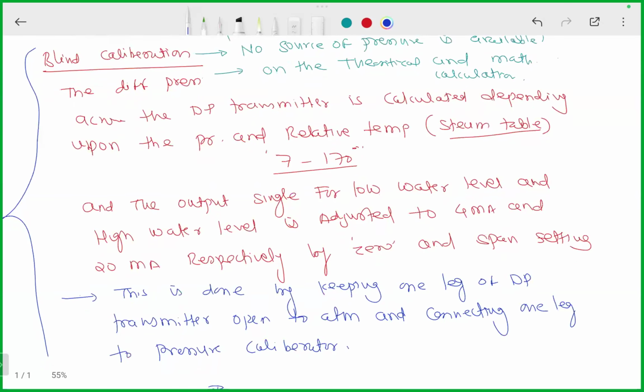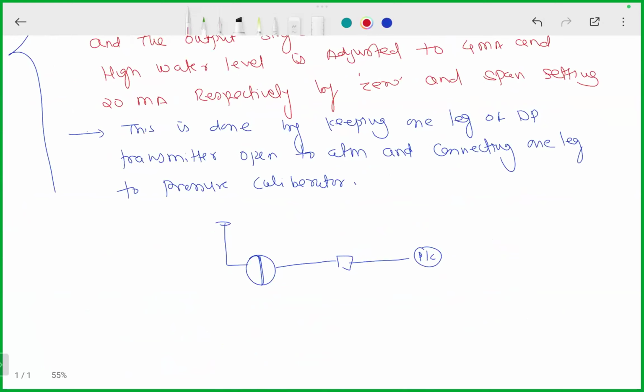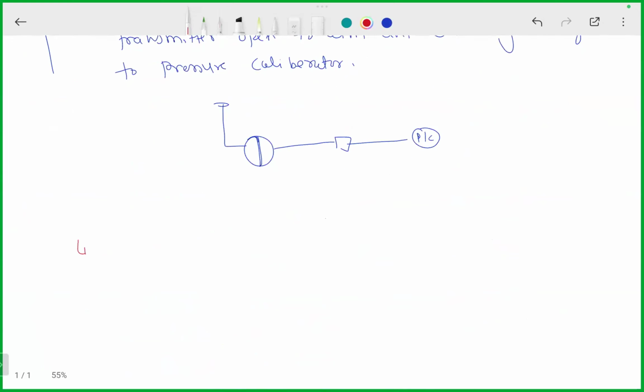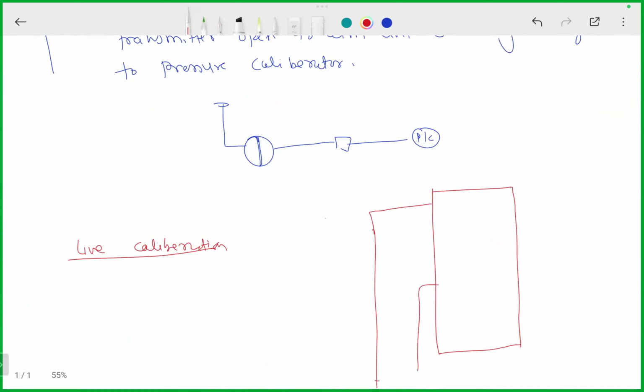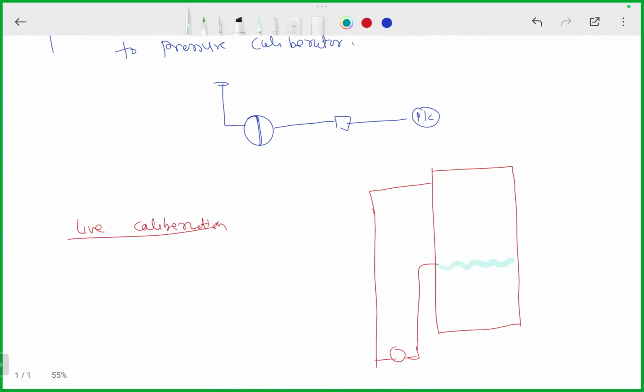What we are going to do in the live calibration? We are going to practically do it on the two sides of the DP transmitter. Practically you are going to bring the level to low level and you are going to adjust the output signal from DP transmitter to be read as 4 milliamp.